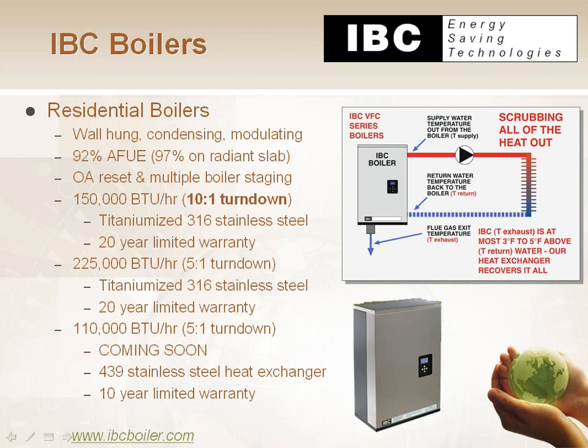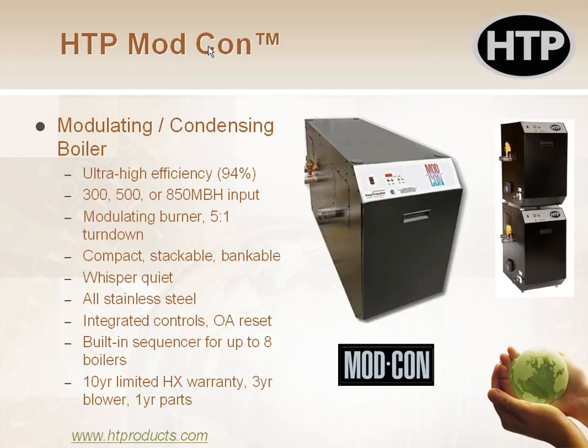The efficiency of the boiler itself doesn't change based on the season, right? Well, I guess it does slightly because the outside combustion air that you're bringing in might have an effect on it. So in the wintertime, like for example, the last one was 94% efficient for that ModCon, right? He's 94% efficient in the wintertime. In the summertime, he might be a slight hair better than that because he's not taking in 0-degree combustion air. He's taking in 80-degree or 90-degree combustion air. But it's going to be really small. Instead of 94%, it'll be like 94.2 or something like that. There's no efficiency loss for running it in the summer. It's actually a slight efficiency gain.